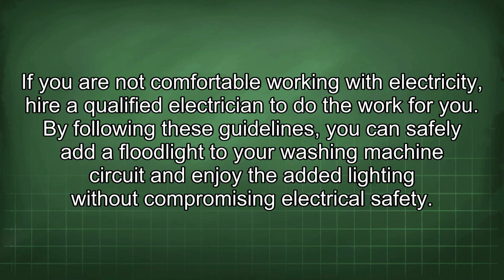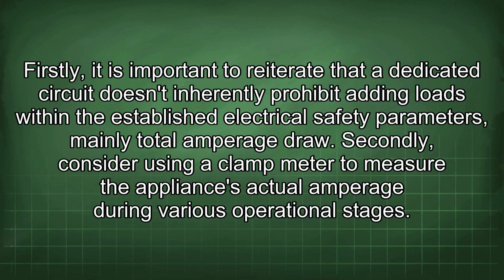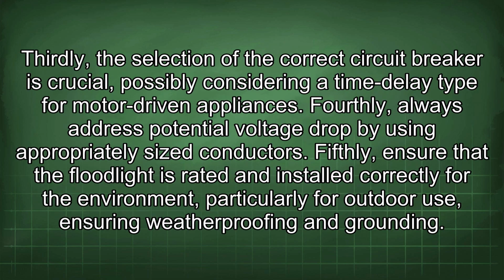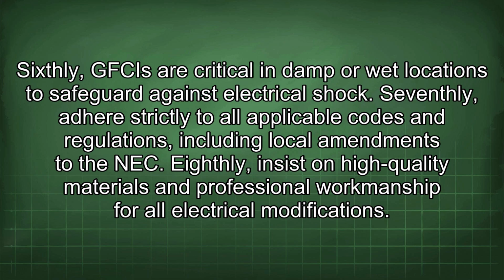without compromising electrical safety. Firstly, it is important to reiterate that a dedicated circuit doesn't inherently prohibit adding loads within the established electrical safety parameters, mainly total amperage draw. Secondly, consider using a clamp meter to measure the appliance's actual amperage during various operational stages. Thirdly, the selection of the correct circuit breaker is crucial, possibly considering a time delay type for motor-driven appliances. Fourthly, always address potential voltage drop by using appropriately sized conductors. Fifthly, ensure that the floodlight is rated and installed correctly for the environment, particularly for outdoor use, ensuring weatherproofing and grounding. Sixthly, GFCIs are critical in damp or wet locations to safeguard against electrical shock.